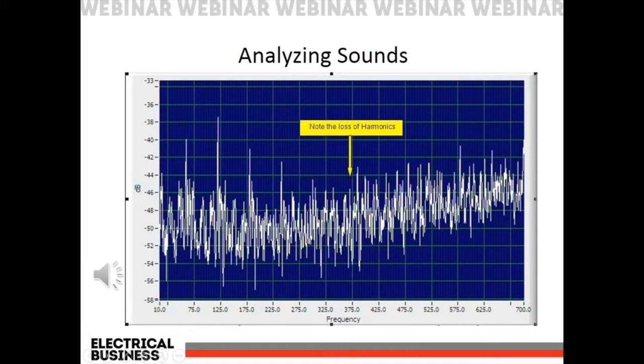But as we continue down the spectrum and go further away, we start to lose those harmonics, and that becomes evident because the flashover is now taking over our rich 60 hertz. We don't lose our line frequency unless something is off. So in this case, the actual flashover that's occurring, causing those pops, is covering up our before rich 60 hertz harmonics, and that's why we're starting to see a difference.